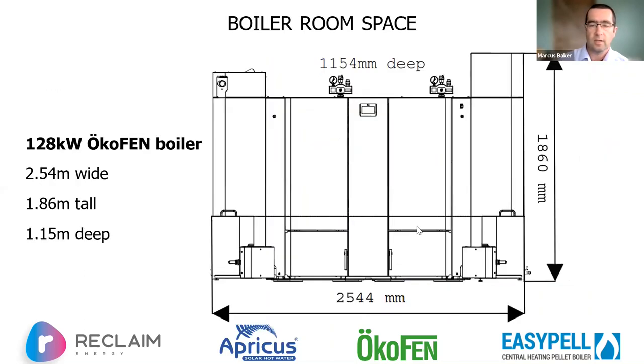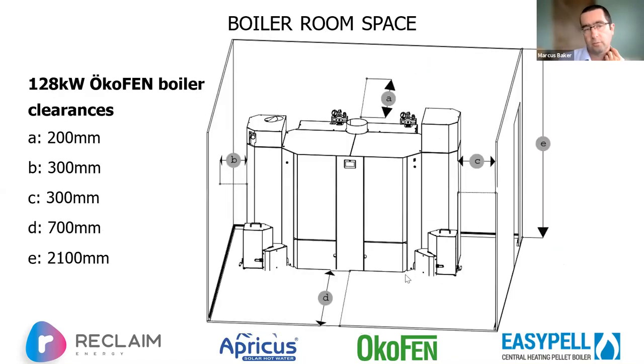So just looking at that, I'm going to use Okofen as an example, but they are more or less much of a muchness in terms of size once we get to these capacities. So 130 kilowatt Okofen boilers, 2.5 meters wide, it's just under 2 meters tall, and it's about 1100 deep. So then you've also got some clearances to bear in mind. They're pretty tight. They're not based on temperature. They're based on servicing. Because we've got a controller on the boiler, we've got wires actually running all the way round and through inside between the casing and the insulation jacket. And we've got motors and augers and all sorts of electrical stuff that doesn't really appreciate getting hot. The outside of the boiler is not hot. And therefore, these clearances are really just minimums for allowing a bit of access for working.